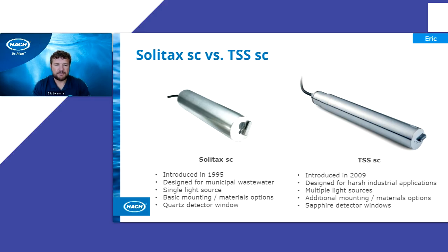We have two different options when it comes to probes. In 1995, the Solitax SC came out, which is designed for municipal applications. It has a quartz detector window. In 2009, we came out with the TSS SC, which is designed more for harsh, industrial applications. It has a sapphire detector window, a harder material than the quartz. So again, it comes down to what application you're trying to measure your solids or TSS in.